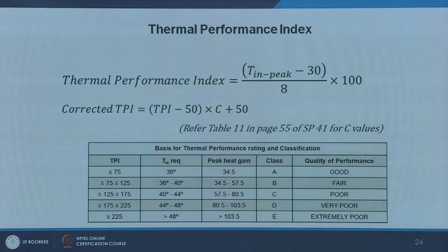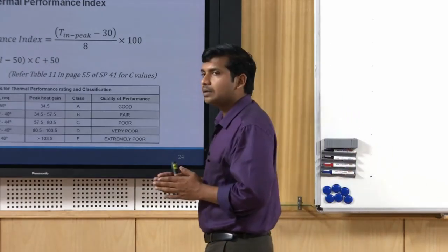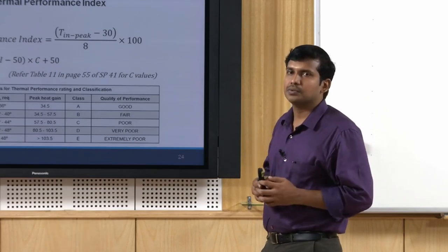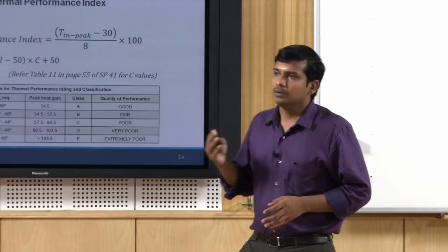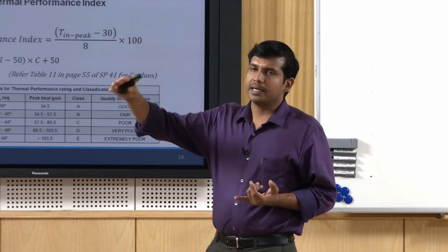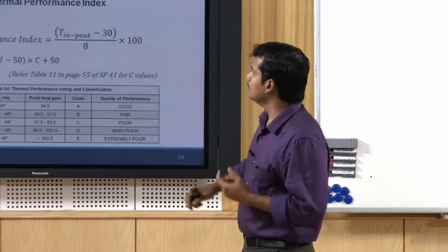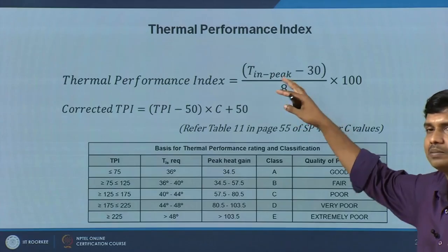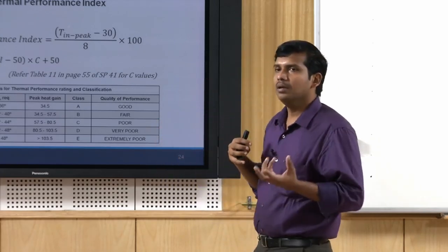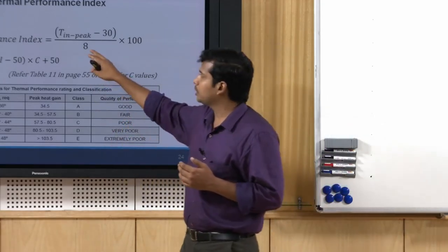Relating back to a previous module on thermal comfort — radiant asymmetry — we discussed allowable cold wall versus hot wall conditions. ISO and ASHRAE codes specify the allowable increase in wall surface temperature compared to air temperature beyond which radiant discomfort is felt. The national code (developed in the 1970s and 80s) estimated that up to 38 degrees surface temperature, radiant discomfort will not be much impactful; beyond 39 to 40 degrees it causes more problems.